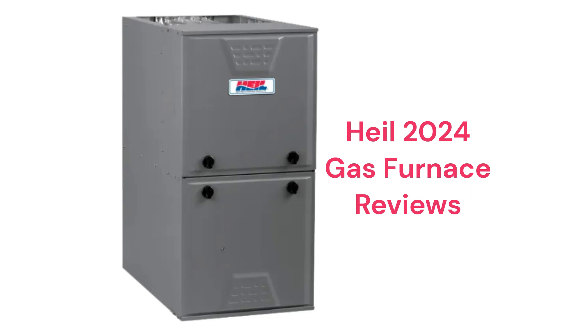The brand is backed by a pretty good guarantee, but they use aluminized steel primary heat exchangers which resist corrosion but are not as durable as brands that use stainless steel. The units use hot surface ignition, which is quieter and more reliable than brands that use spark ignition.